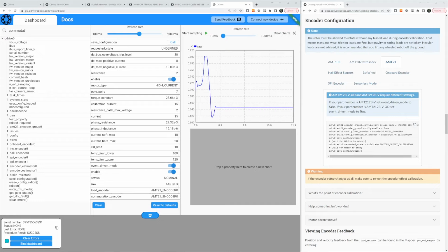What this does is rotate the motor by energizing the coils, and then seeing what the encoder does in response, and that helps align the motor's rotor phase to the encoder. We don't assume any particular angle offset between the encoder and the motor, so that's why that's calibrated. If you do disassemble the motor and encoder and put them back, essentially if you disassemble it at all, I would recommend that you rerun the encoder offset calibration.